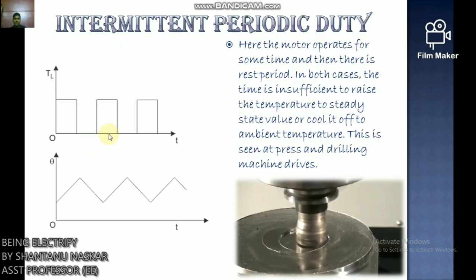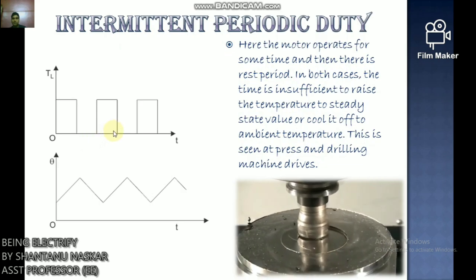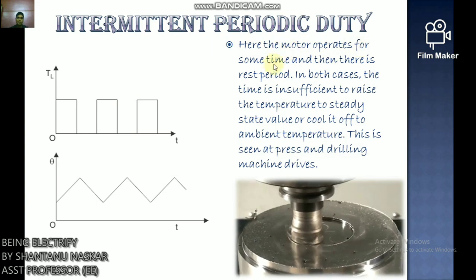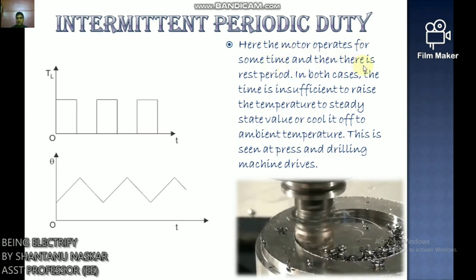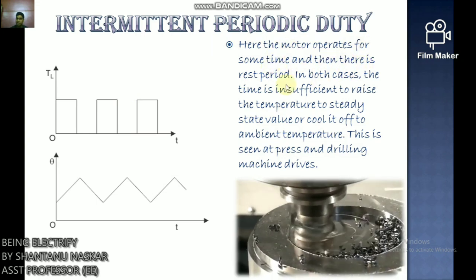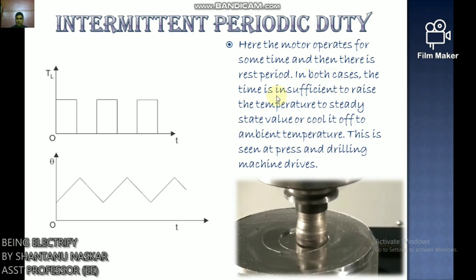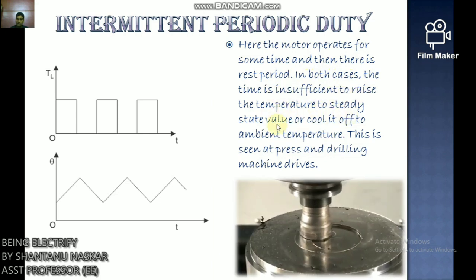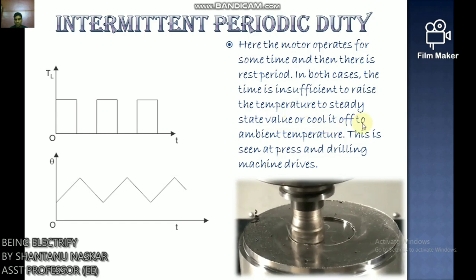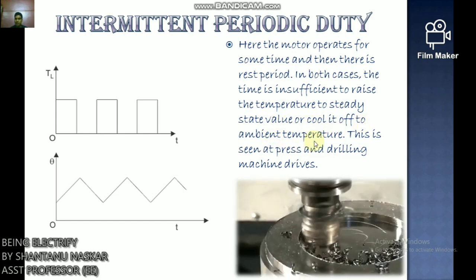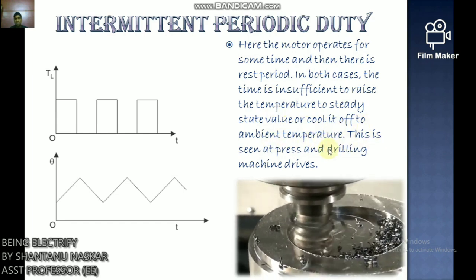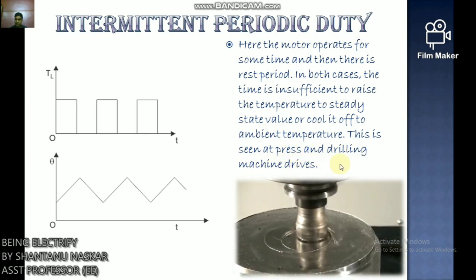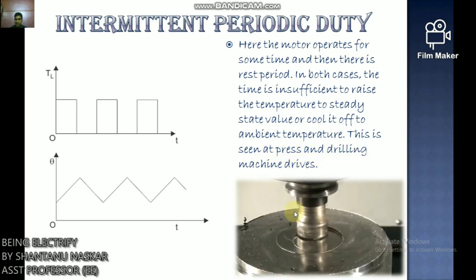Intermittent periodic duty: The motor operates for some time and then there is a rest period. In both cases the time is insufficient to raise the temperature to steady state or cool it to ambient temperature. This is seen in pressing and drilling drives.